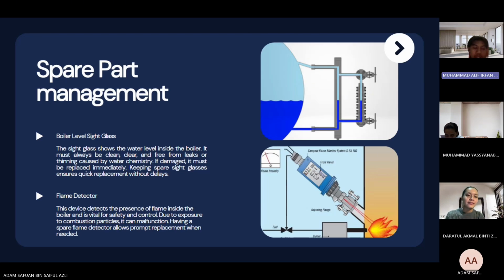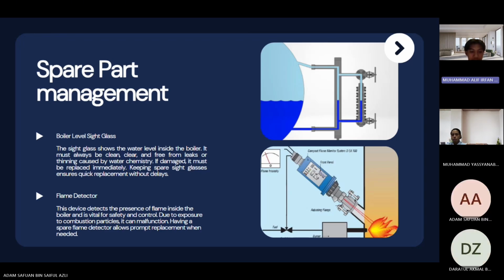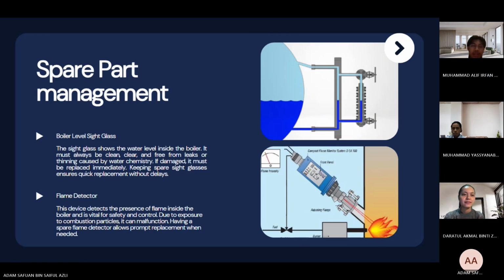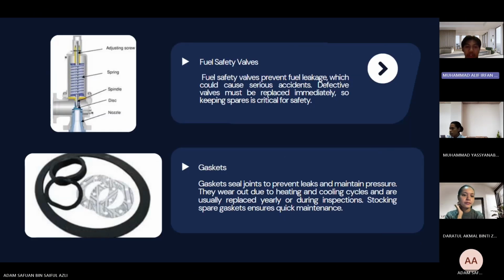Second, flame detector. This device detects the presence of flame inside the boiler and it is vital for safety and control. Due to exposure to combustion particles, it can malfunction. Having a spare flame detector allows prompt replacement when needed. Third, fuel safety valve. The fuel safety valve prevents fuel leakage, which could cause a serious accident. A defective valve must be replaced immediately, so keeping a spare is critical for safety.